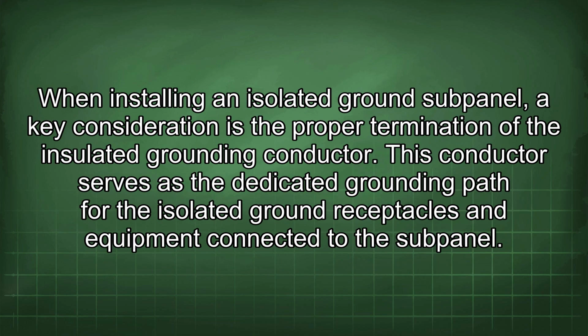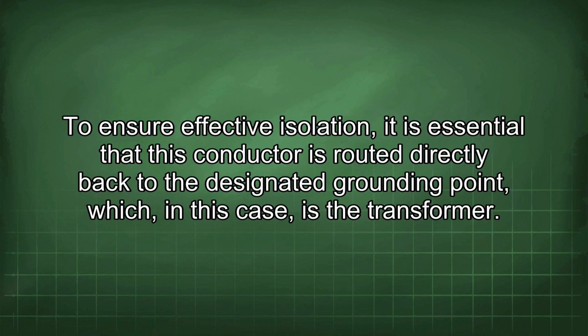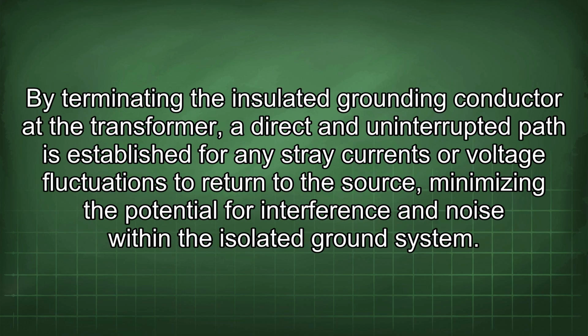When installing an isolated ground subpanel, a key consideration is the proper termination of the insulated grounding conductor. This conductor serves as the dedicated grounding path for the isolated ground receptacles and equipment connected to the subpanel. To ensure effective isolation, it is essential that this conductor is routed directly back to the designated grounding point, which, in this case, is the transformer. By terminating the insulated grounding conductor at the transformer, a direct and uninterrupted path is established for any stray currents or voltage fluctuations to return to the source, minimizing the potential for interference and noise within the isolated ground system.